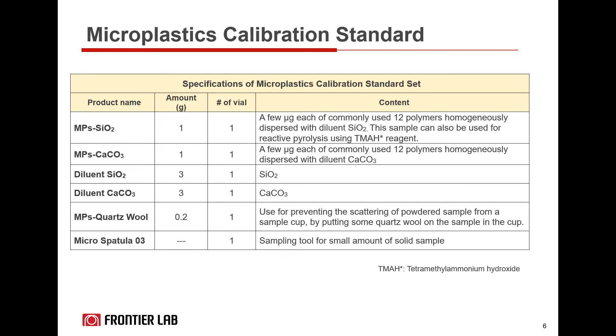So now that you have that set with 2 or 3 different types of calibration standards, how would you choose which calibration standard you would like to use as the first step? This table here can guide you to select the appropriate microplastic calibration standard. You can select the type of standard based on your target microplastic polymers. Now, if you don't have any targets at first, we suggest that you start with MP's CaCO3 standard that can target pretty much all the 12 polymers, but with low sensitivity to PET.